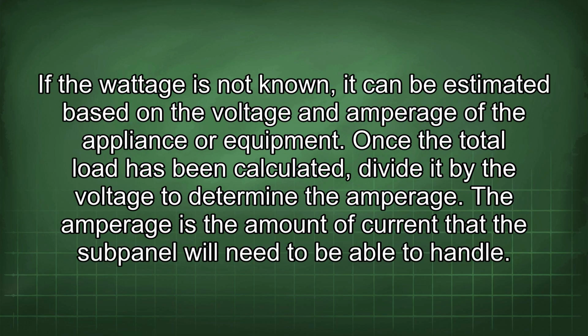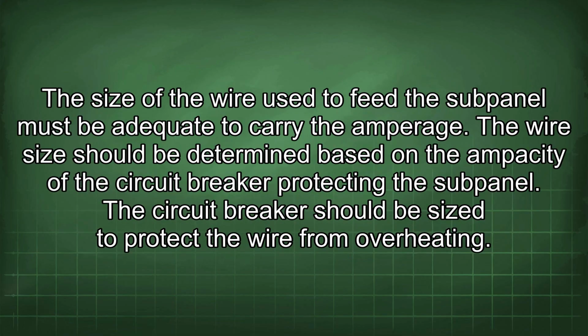If the wattage is not known, it can be estimated based on the voltage and amperage of the appliance or equipment. Once the total load has been calculated, divide it by the voltage to determine the amperage. The amperage is the amount of current that the subpanel will need to be able to handle. The size of the wire used to feed the subpanel must be adequate to carry the amperage.